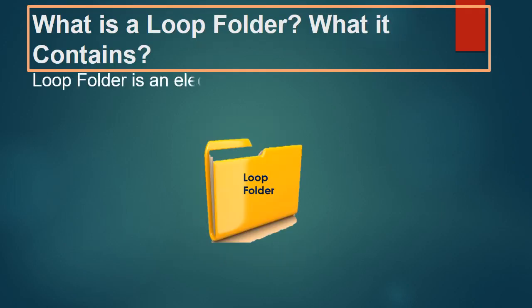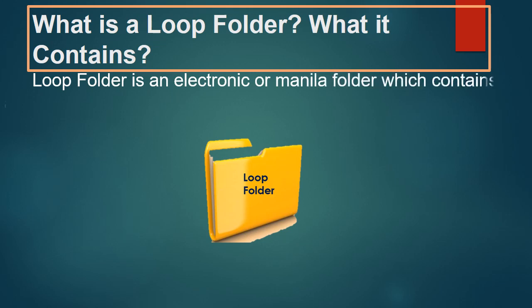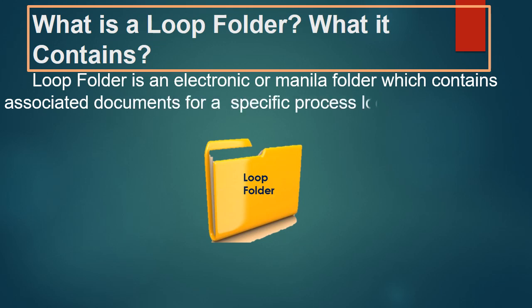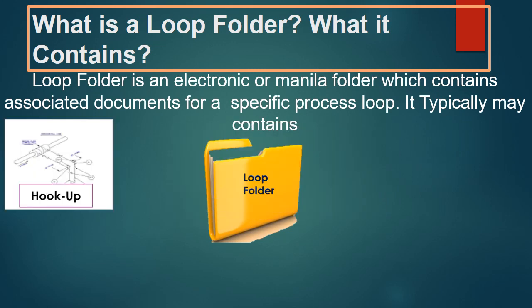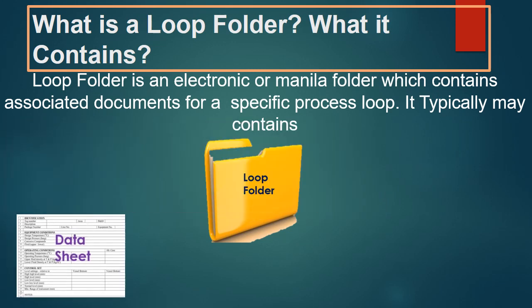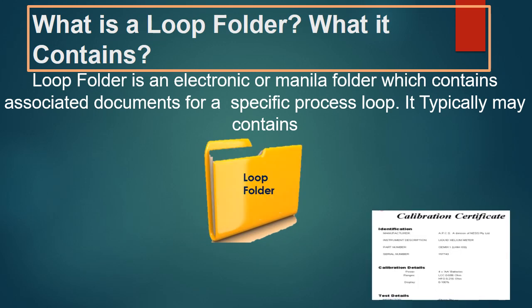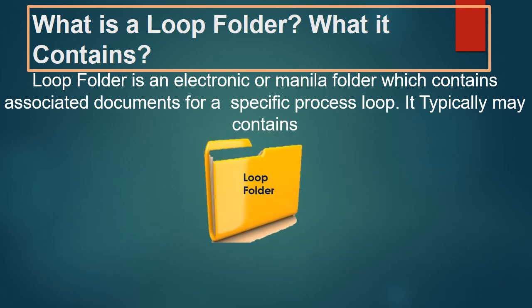What is a loop folder? A loop folder is an electronic or manila folder which contains associated documents for a specific process loop. It typically contains the P&ID diagram, hookup diagram, instrument data sheets, calibration reports, and loop diagram.